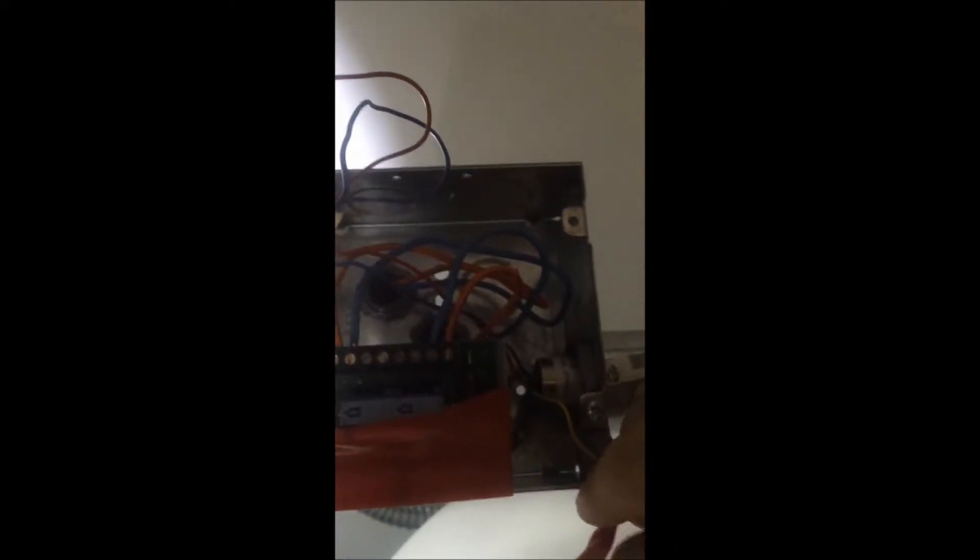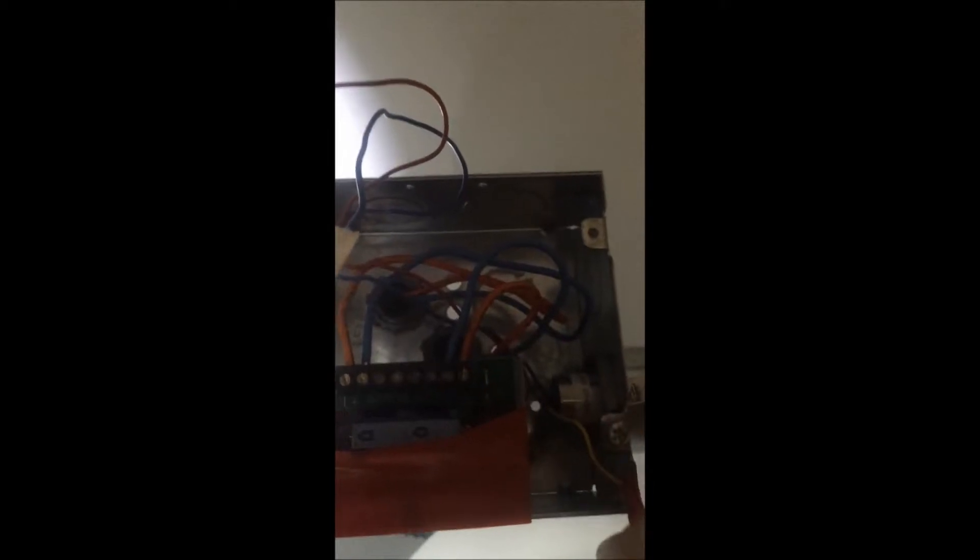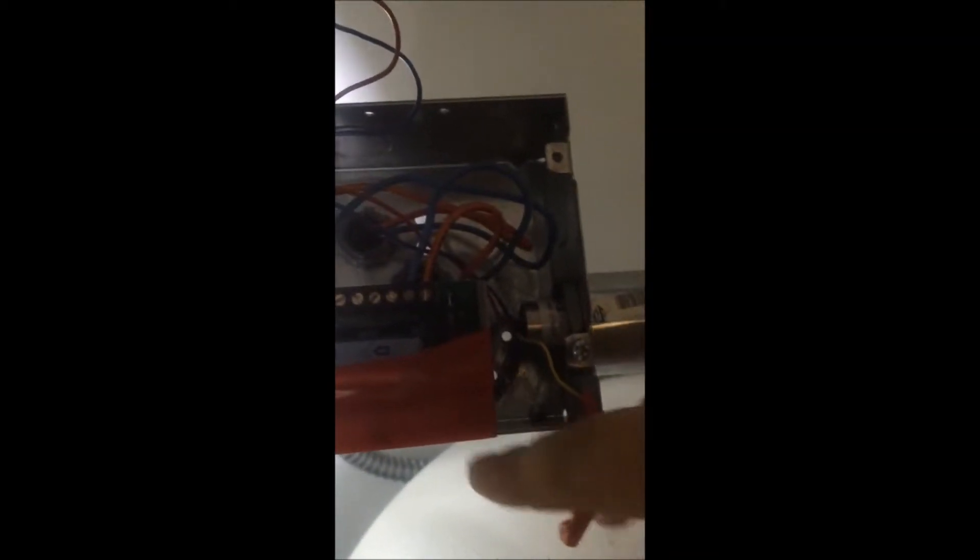Alright, so we've got your FM-200s. They all jump together. Now this junction box right here is where the squib sits. This little silver thing's a squib. All of them have four wires, but the green and yellow are capped off together down here - they're not going to anything.